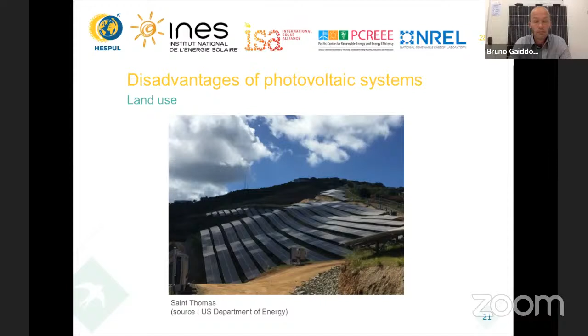And in a diesel microgrid, there's a limit. You can't install as much PV as you want. The technical limit comes from the gensets. To keep the microgrid stable, you need to always run the genset at a power above 30% of its nominal power. Actually, this rule is the limit to install a PV system on microgrids. Otherwise, if you go below 30% of the nominal power of the genset, you will negatively affect the units. So this is why it's recommended never to run a genset under 30% of its nominal power.